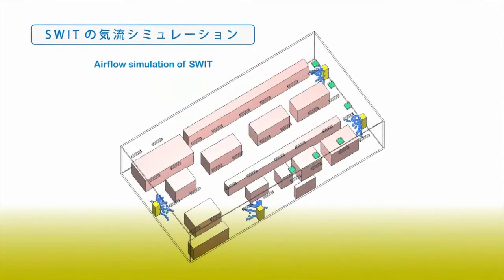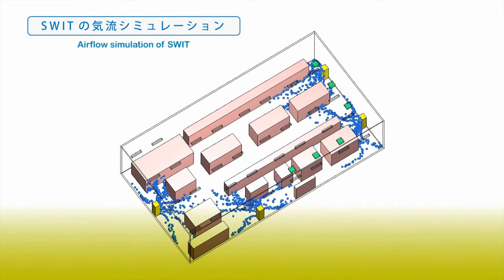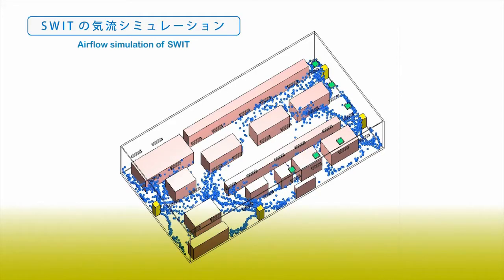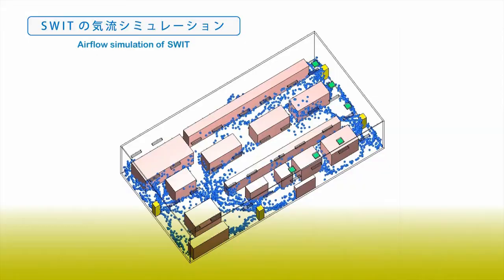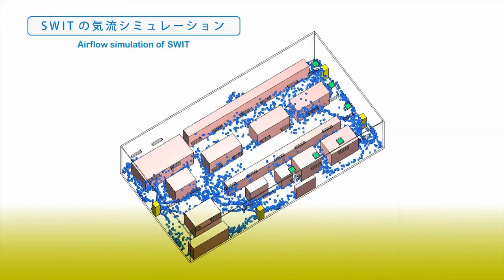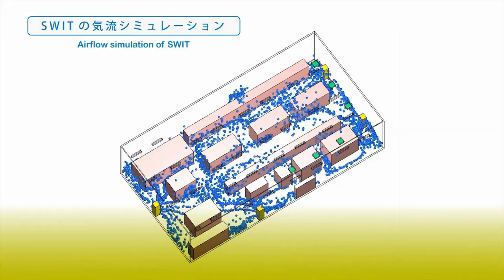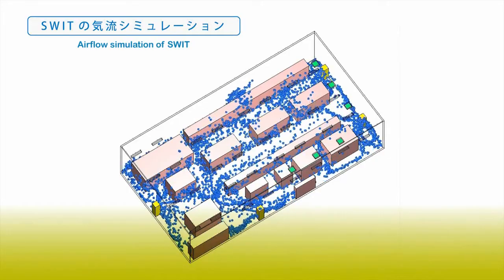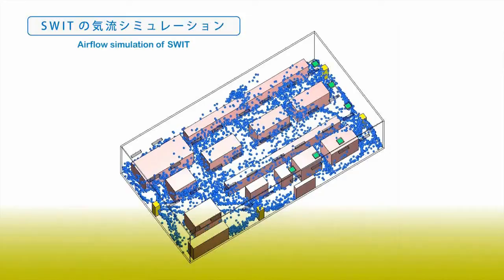Airflow simulation of SWIT. Let's take a look at an airflow simulation in which SWIT is applied in an electrical room. Even if there are devices and obstacles blocking the flow, the air is supplied to every corner of the room. Even if the location and layout of the devices are changed, there will be no construction modifications required to change the air outlet positions.